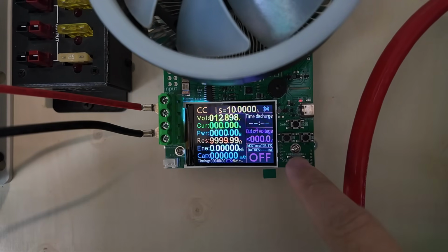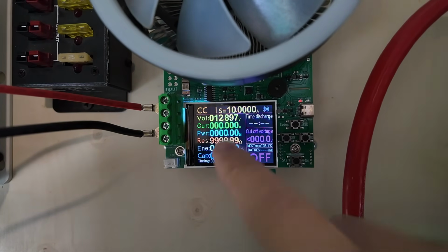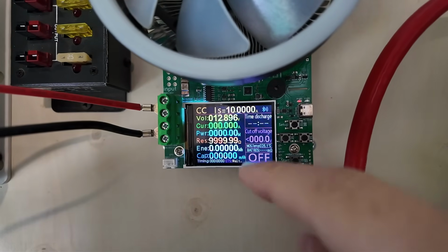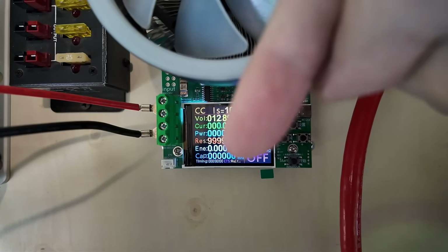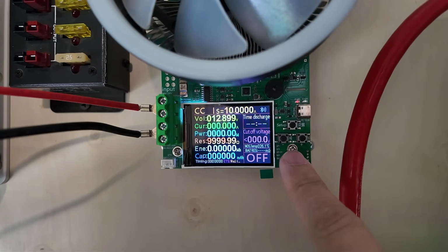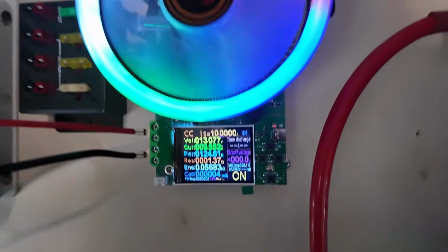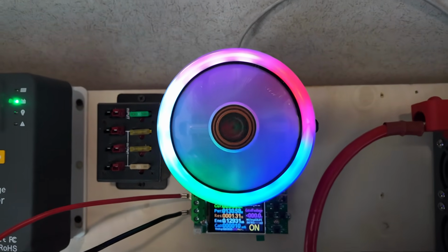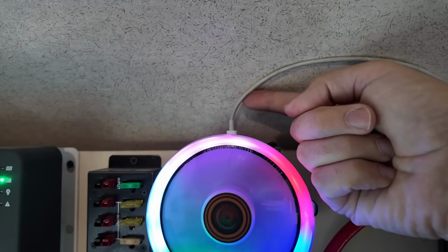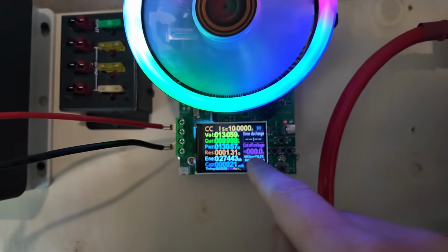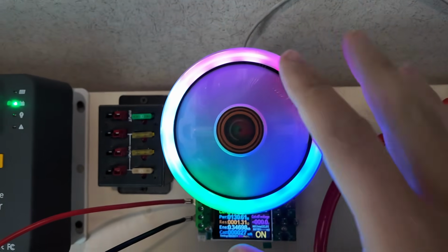So when I hit this button down here in the corner, it's going to start the test, and the little computer in here is going to try to maintain a 10 amp continuous discharge from the battery. And we're off. This whole thing has a separate power supply, so all the power required to run the display, the computer, the fan, and the lights is not coming from the battery. All that thing is doing is taking battery power and turning it into heat in my room. Luckily the temperature isn't too hot today, so having a little heater in here is going to be helpful. Round 1 battery test done.